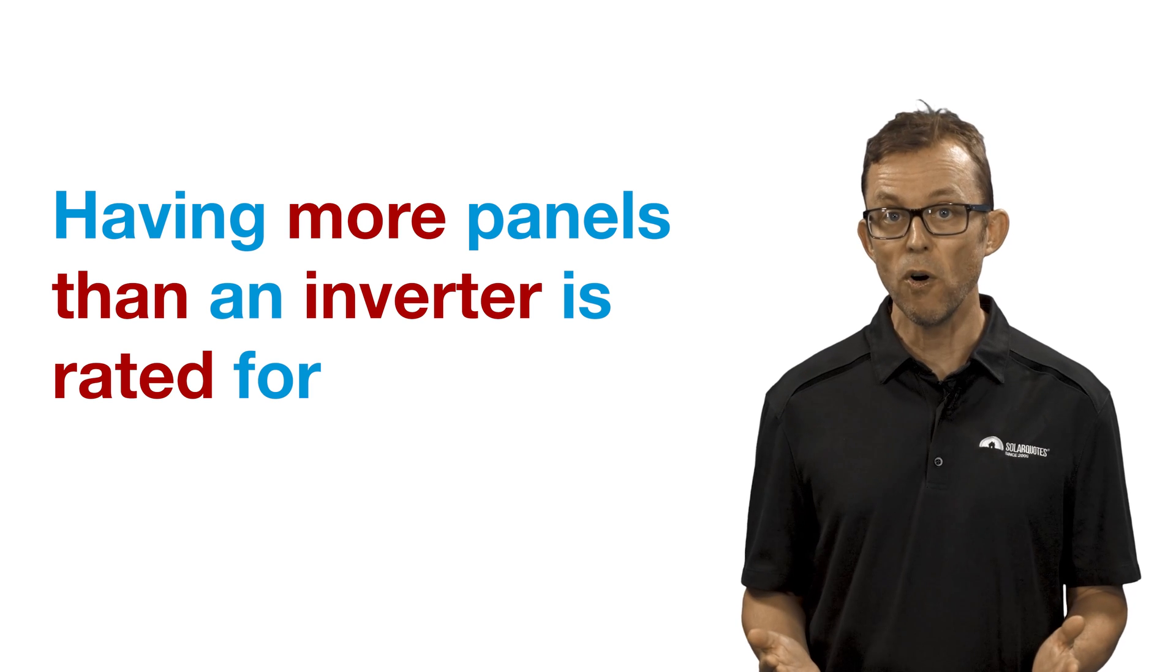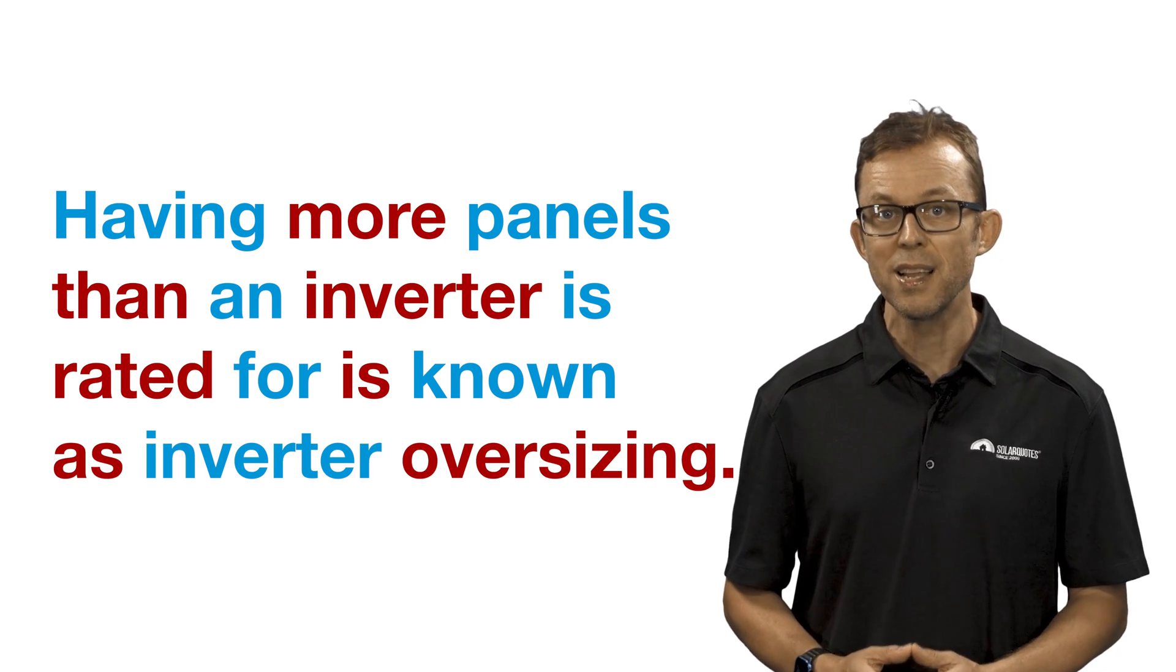Next up, solar inverters and oversizing. I get emails all the time saying, I've got a quote for solar. They offered me a five kilowatt inverter and 6.6 kilowatts of panels. What's going on? Am I going to blow up the inverter? Having more panels than an inverter is rated for is known as inverter oversizing. And it's often a smart design move for a few reasons.